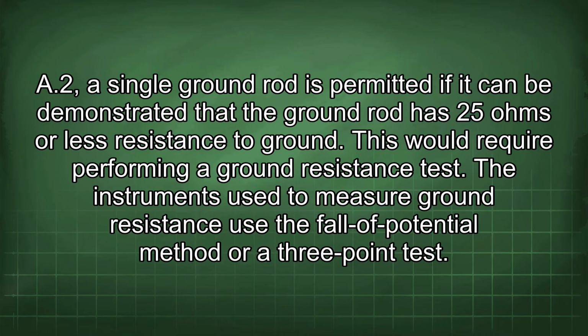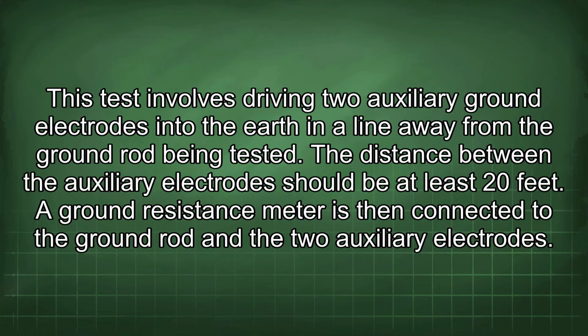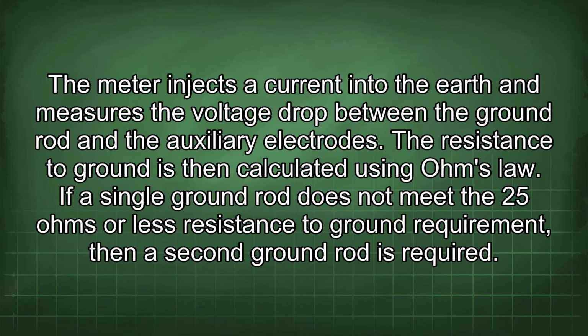The instruments used to measure ground resistance use the fall-of-potential method or a 3-point test. This test involves driving 2 auxiliary ground electrodes into the earth in a line away from the ground rod being tested. The distance between the auxiliary electrodes should be at least 20 feet. A ground resistance meter is then connected to the ground rod and the 2 auxiliary electrodes. The meter injects a current into the earth and measures the voltage drop between the ground rod and the auxiliary electrodes. The resistance to ground is then calculated using Ohm's law.